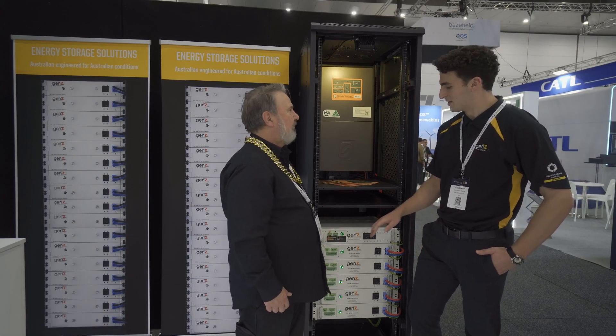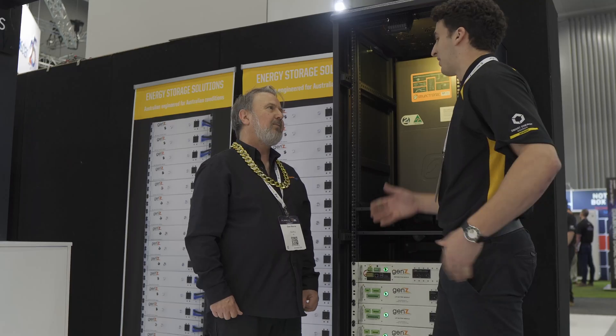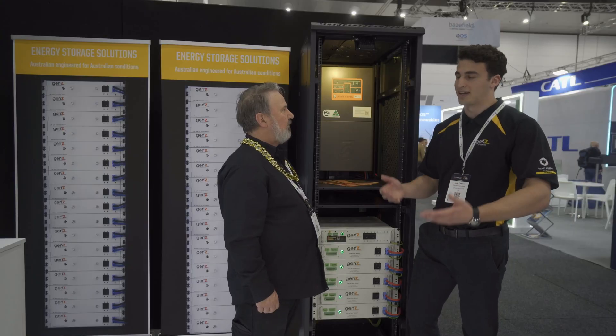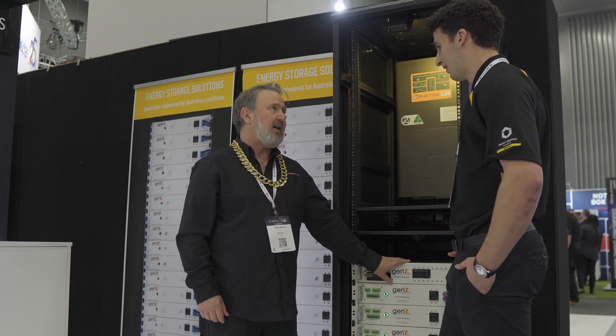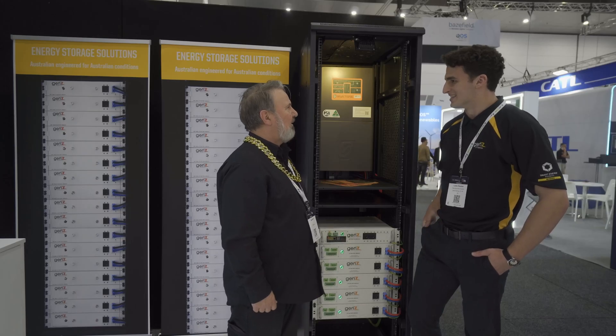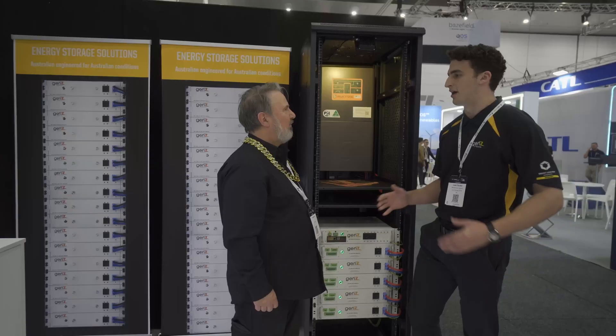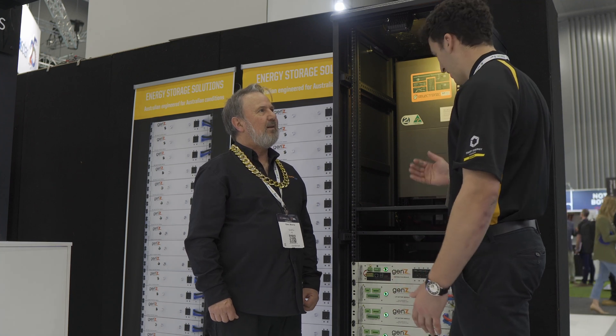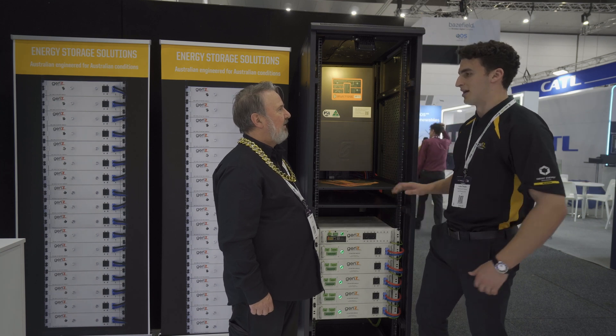And where does it go? We use what we call the Z Data Controller. What this does is it aggregates all the data from the batteries and puts it into one display, which we can then give to our customers. This unit here is an aggregator of data, but it's got a lot of plugs on the back — it does more than just aggregate data. It's an easy parallel module and acts as a final point of demarcation for the rack itself. It has ports at the back where we can wire these batteries directly in and then use the circuit breakers at the front to control the final output of the rack.